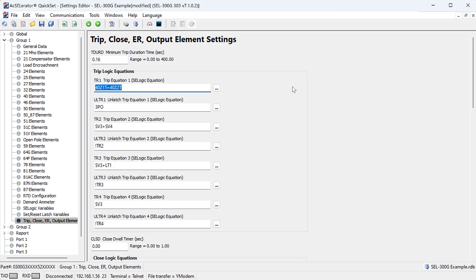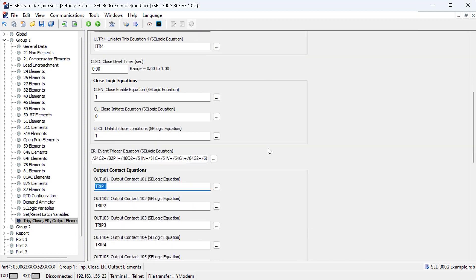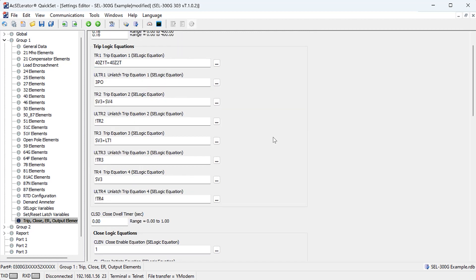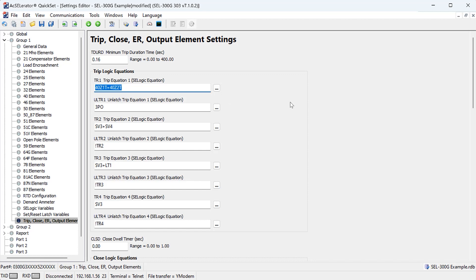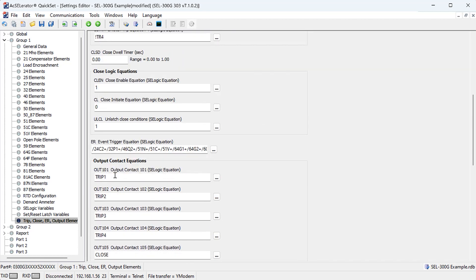Going back to the settings file, we program the trip equation. We need to program the outputs of zone one and zone two loss of field elements into the trip equation, and then that trip equation to the output contact that will physically trip the breaker. Under Group 1, Trip/Close/Other Output Elements, we use trip equation number one and program it as 40Z1T OR 40Z2T. Then we program trip equation one to output OUT101, which is the output wired to the trip coil or lockout relay.